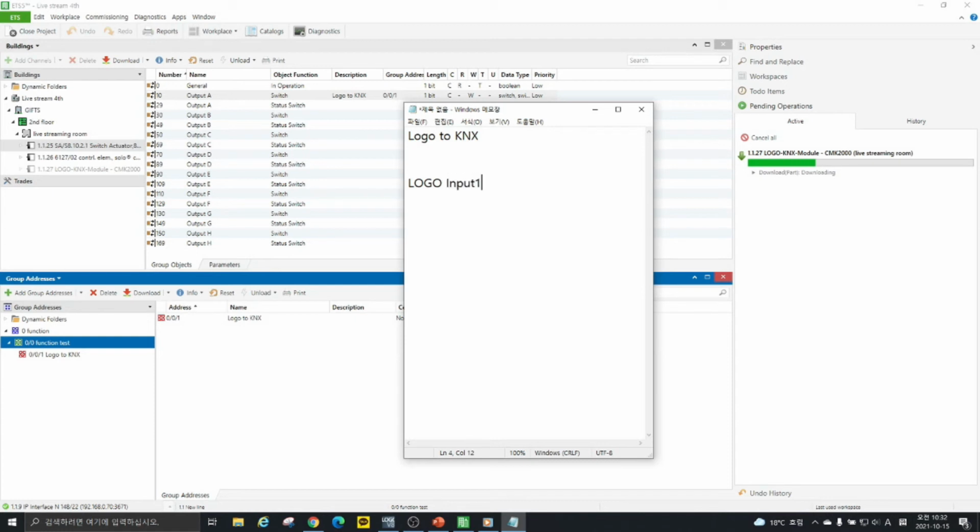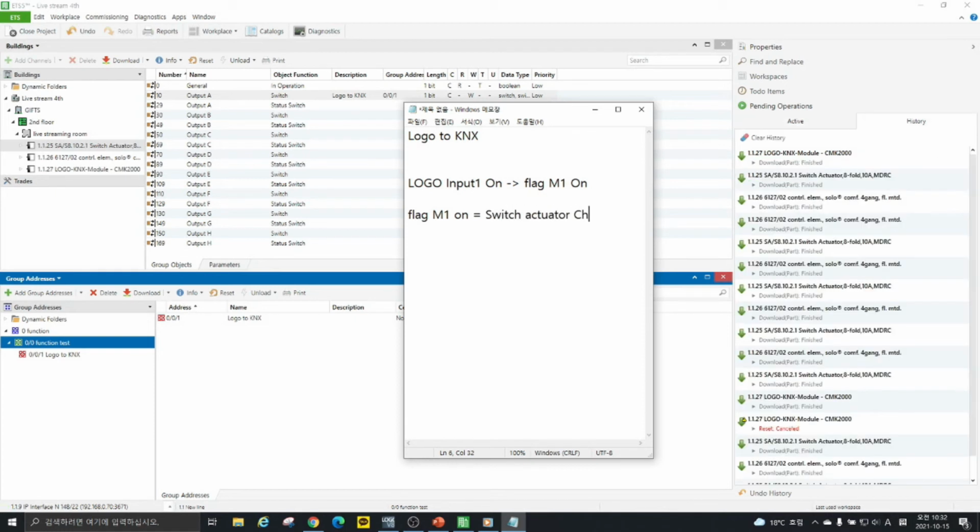동작을 설명드리면은 로고 인풋 1을 온 하게 되면은 여기서 플래그 M1이 온 되게 됩니다. So to give you the detailed explanation about the function programming, what I just said, so if you turn the input 1 in the logo program, the flag M1 has been on. 그리고 이제 우측에 보시면은 제가 이제 플래그 M1과 스위치 액추에이터 채널 A를 매칭을 시켜놨기 때문에 이 M1이 온 됐을 때 이 채널 A가 같이 온 되게 됩니다.